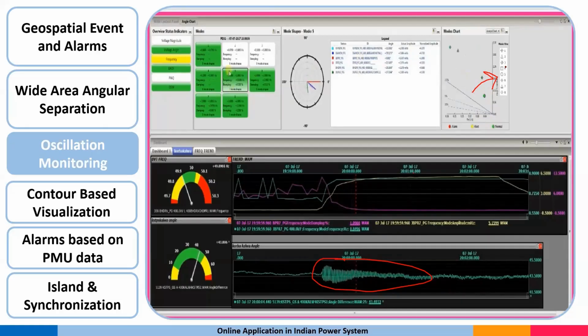So electromechanical oscillations are basically in the range of 0.1 hertz up to 4 hertz in the power system. Maximum it usually goes up to 3 hertz, but somewhere it can go up to 4 hertz also. My sampling frequency was 25 hertz, so I can measure up to 12.5 hertz oscillation with respect to the Nyquist criteria, and the oscillatory frequency of electromechanical oscillation is 0.1 to 4 hertz.